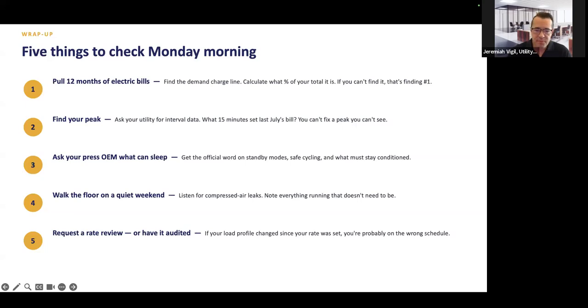Ask your utility for interval data. What I mean by interval data is they'll tell you what your demand load is every 15 minutes, every day, for however many years you requested. Find that interval data, because if there's just one bill in July, or one 15-minute period where it peaked too much, it's determining what you're being charged for demand for the rest of the year, even though you're not using what that one peak was. So request interval data, find that peak, determine what happened during that one 15-minute period if you can, see if you could avoid it and move forward that way. That way you're not being penalized for a one-time 15-minute error that took place a year ago.